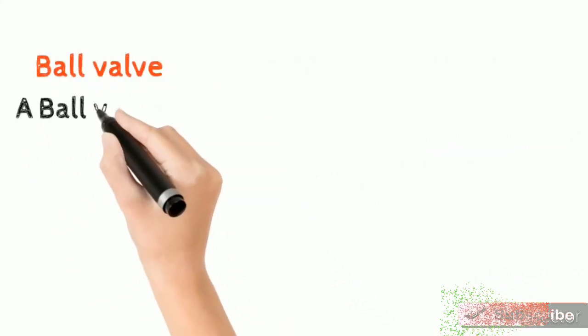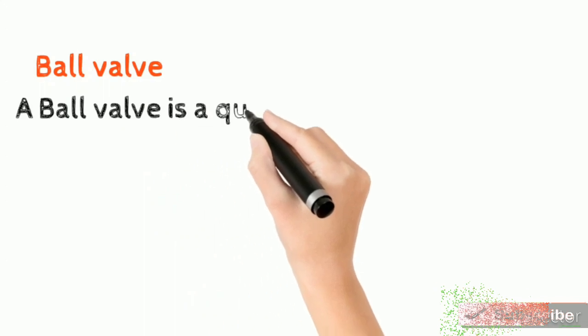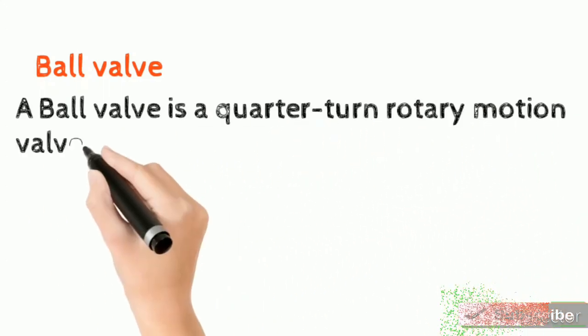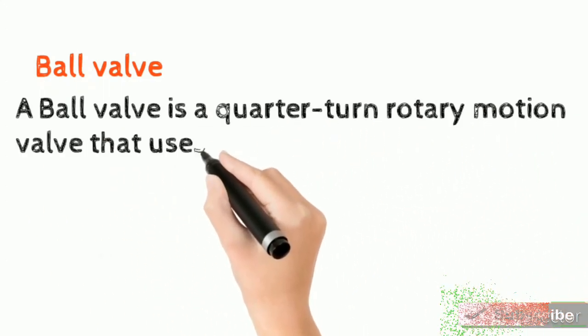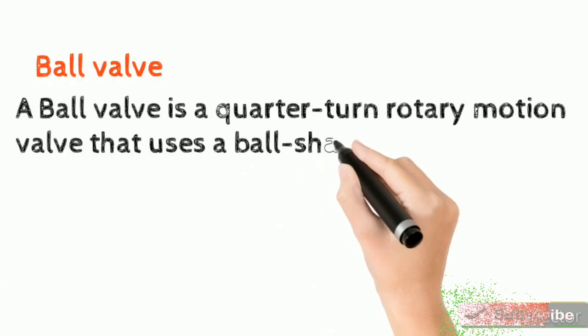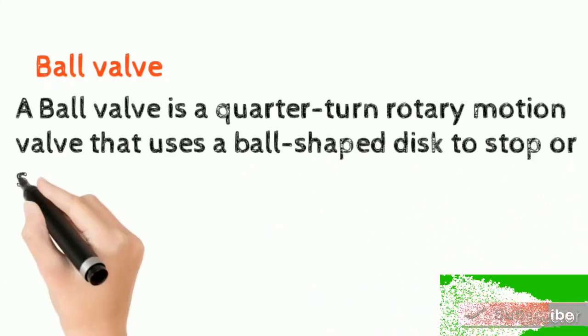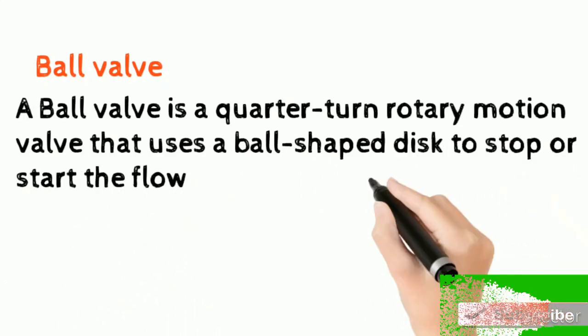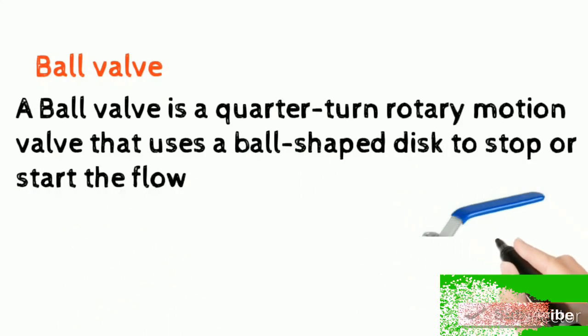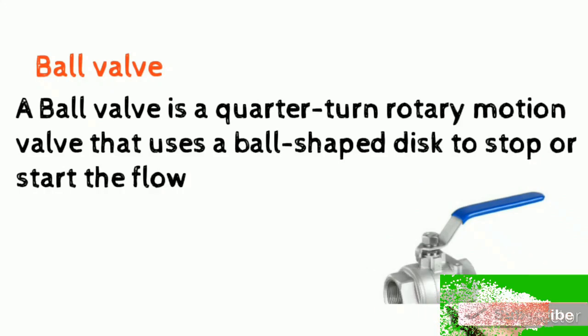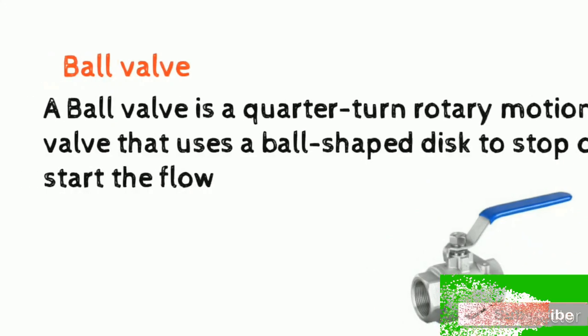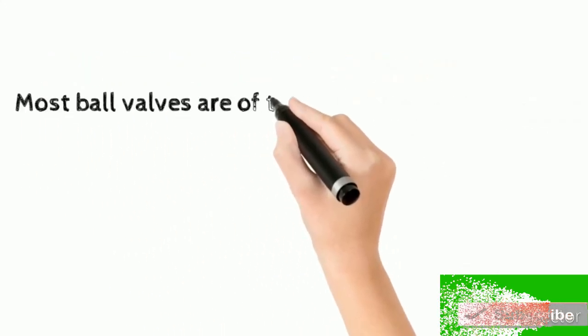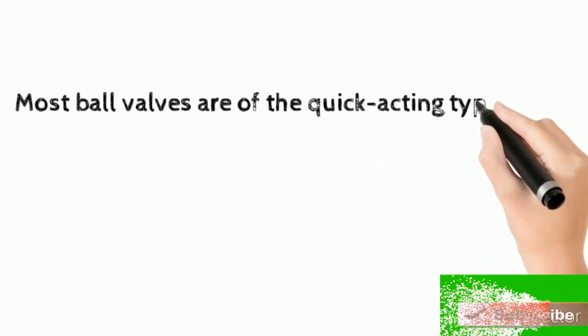The ball valve is a quarter turn rotary motion valve that uses a ball-shaped disc to stop or start the flow. Most ball valves are of the quick acting type, which requires a 90 degree turn of the valve handle to operate the valve. The ball valve is smaller and lighter than a gate valve of the same size and rating.